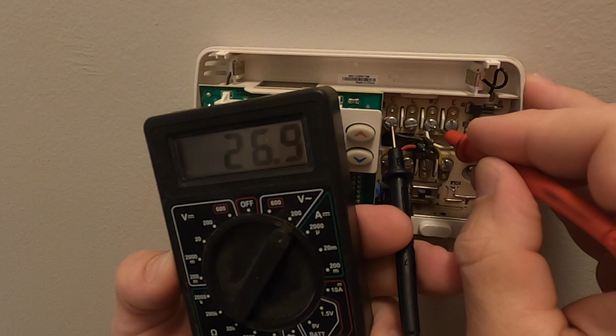So, yep, we have voltage here. Of course, that's jumped, so it's going to show on either one. So we know that somewhere we're getting voltage on our white wire that's calling for the auxiliary heat to come on, even though we're calling for cool as well. So we're going to have to go downstairs.